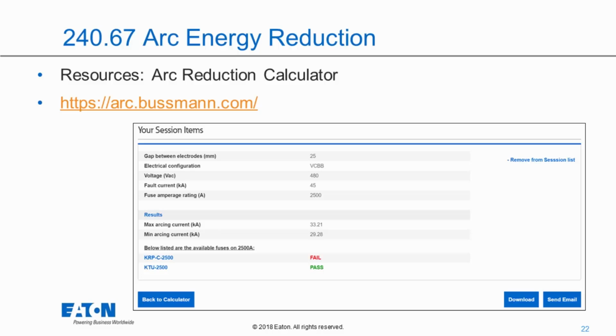So what we've done here is we selected the VCBB orientation. We gave an example here for a 480 volt system, a fault current of 45 KA, and again note the units there, that's 45 KA, not 45 amps. And then the fuse ampacity rating, which we allow you to select between 1200 amps, of course, where the requirement kicks in, and we only allow you to go up to 2500 amps, because what we found is, looking at time current curves and estimated arcing currents, if you get into 3000 amps or higher, you're going to have to use some sort of arc energy reduction technology. So 2500 amps is really the largest ampacity where we have the possibility that we may not have to provide arc energy reduction technology. And what you can see here, you see the corresponding arcing currents.